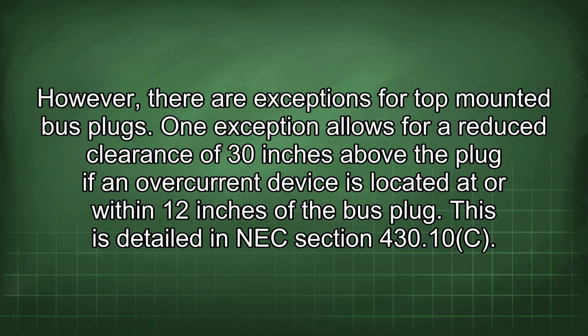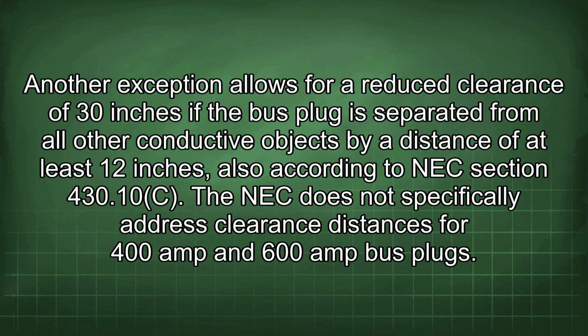One exception allows for a reduced clearance of 30 inches above the plug if an overcurrent device is located at or within 12 inches of the bus plug. This is detailed in NEC section 430.10c. Another exception allows for a reduced clearance of 30 inches if the bus plug is separated from all other conductive objects by a distance of at least 12 inches, also according to NEC section 430.10c.